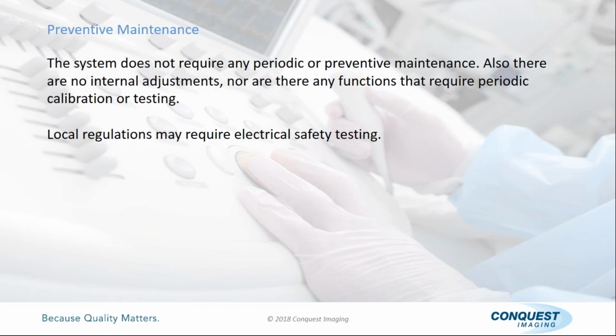But important, okay? Electrical safety, to me, that's the key. What about backing up? Don't you want to back this up? No. The only thing you can back up is your network settings, so you're really limited in what you can do on these, which is good and bad, right? They don't have presets per se to back up. They don't have the traditional backups that you would have on ultrasound. They don't exist on this one, so it's good and bad. Your PM is going to be very, very, very quick.